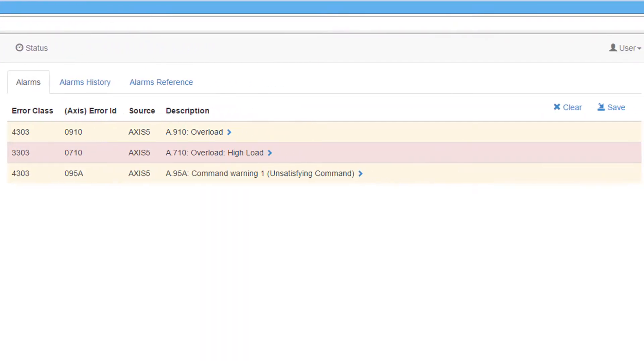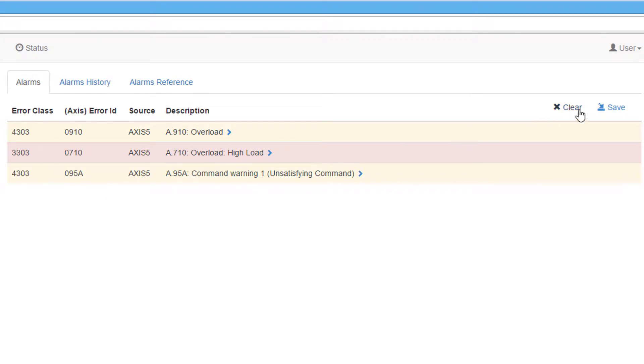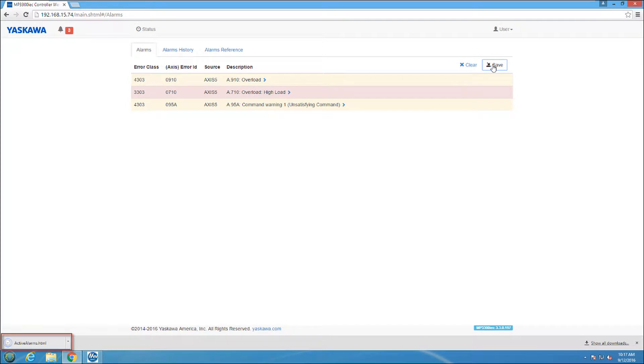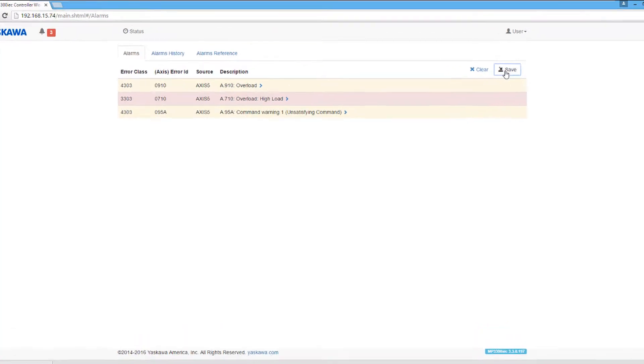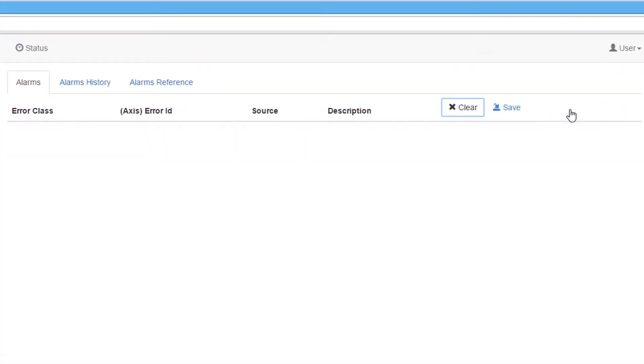The alarms tab shows the current alarms along with their descriptions that are on both the controller and the connected servo amplifiers. I have an A.710 overload alarm. I'll save the alarm and description, which downloads it to my PC as an HTML file. I'll then reset the alarm with the Clear button. It is important to note that only certain alarms can be cleared this way.